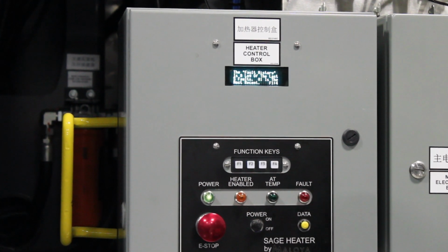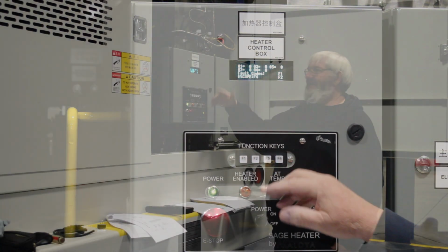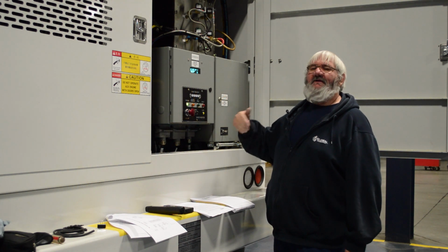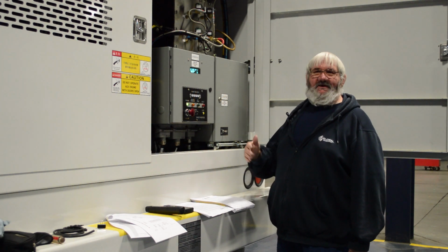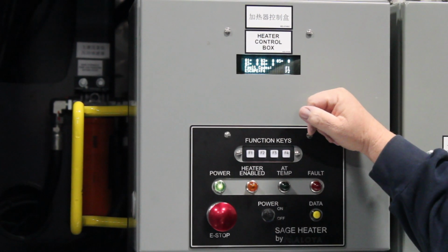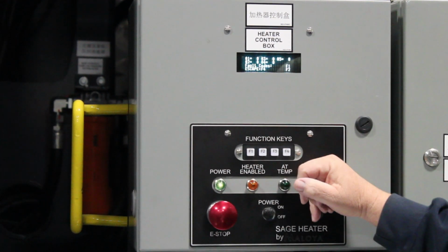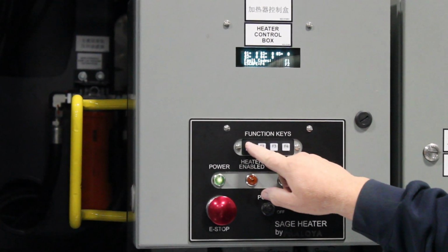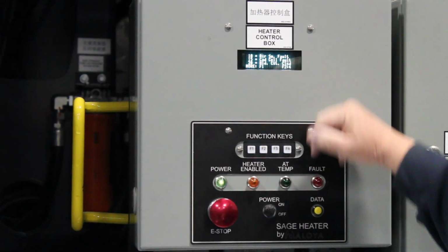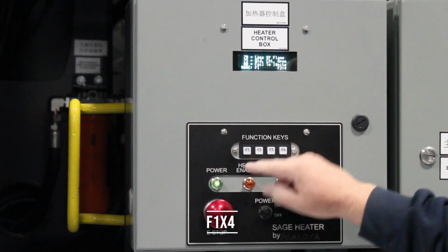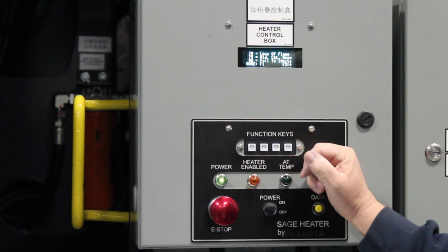Now here again, the fault history is a log of your last 5 faults. Now we're going to scroll down. Now remember, we're just looking at a code 70. Even though we don't have any code 70s in here, this is the one that we're troubleshooting. This is what you would look for. So you would look at your codes. Code 70 is in the one that's been captured. You would scroll down. This would give you a list of your codes. You would keep scrolling down. Code 70, loss of flame.